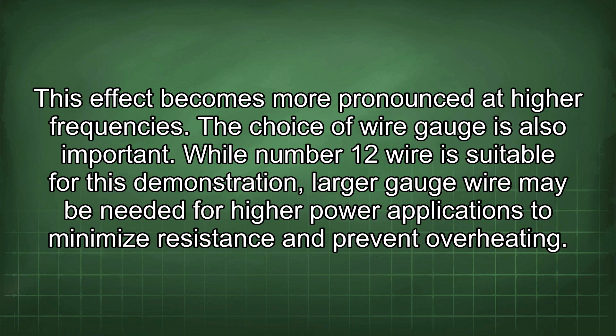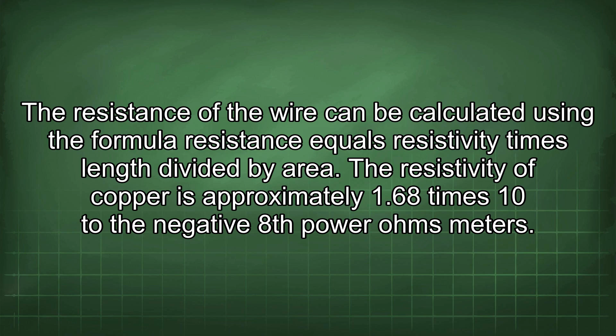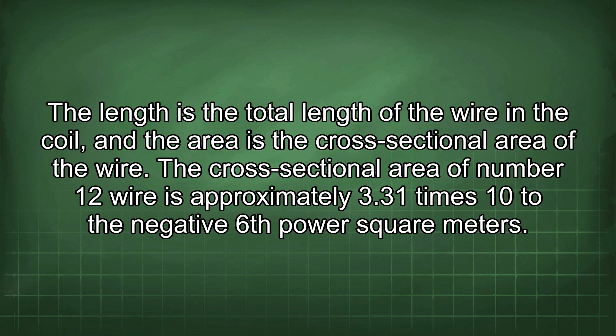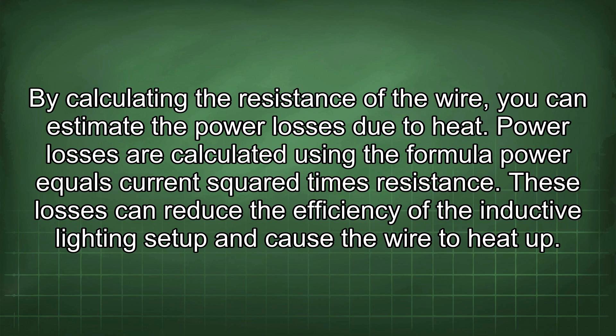The resistance of the wire can be calculated using the formula resistance equals resistivity times length divided by area. The resistivity of copper is approximately 1.68 times 10 to the negative 8th power ohm meters. The length is the total length of the wire in the coil, and the area is the cross-sectional area of the wire. The cross-sectional area of number 12 wire is approximately 3.31 times 10 to the negative 6th power square meters. By calculating the resistance of the wire, you can estimate the power losses due to heat. Power losses are calculated using the formula power equals current squared times resistance. These losses can reduce the efficiency of the inductive lighting setup and cause the wire to heat up.